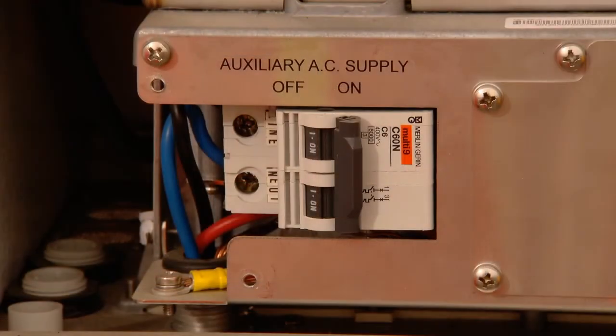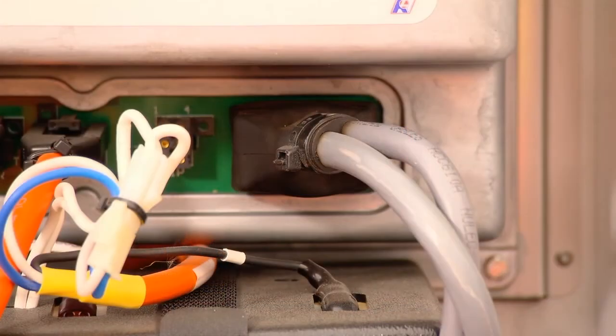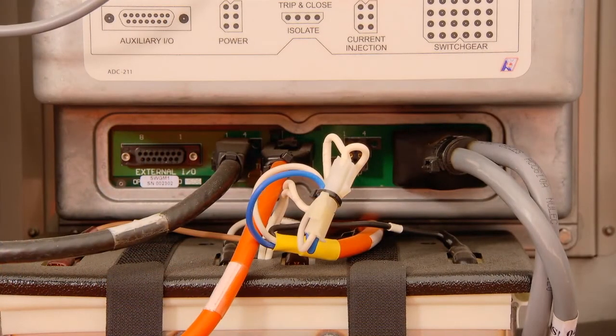The AC supply is controlled by a duplex breaker. If the unit is running on the battery, check this breaker immediately and reset it. The gray cables are the connections from the ADVC control to the reclosers. The interface cables for the ADVC controller and its display unit are connected at this panel.